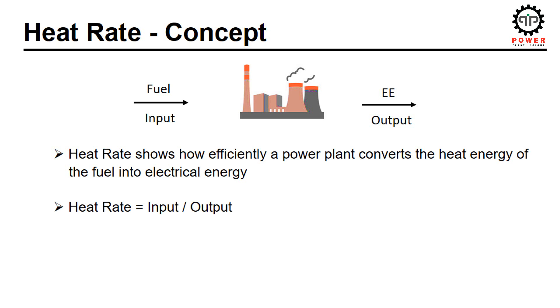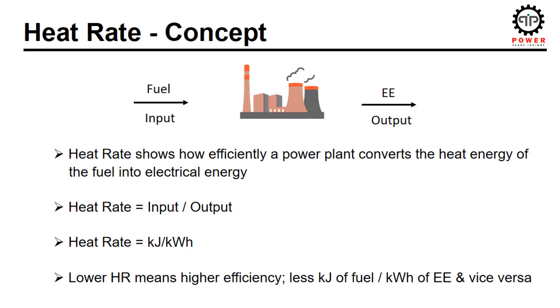Heat rate is the ratio of input to output. In other words, heat rate is the amount of fuel energy consumed to generate per kilowatt-hour of electrical energy. If the value of heat rate is less, it means that its efficiency is higher, because less energy of fuel is required to generate per kilowatt-hour of electrical energy. We will understand these statements when we do an exercise of heat rate calculation at the end.